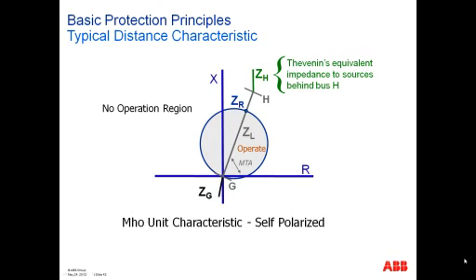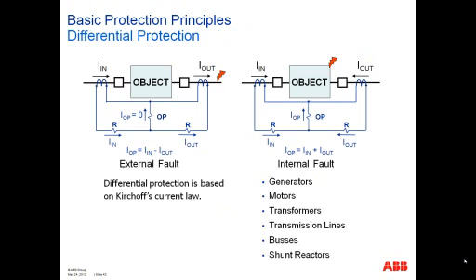Typical distance characteristics. For a mho unit characteristic, which is self-polarized, you have the circular characteristic that goes through the origin and the set reach. And the set reach is, of course, the diameter of the circle there that I show on the impedance plane. The impedance plane shows both the resistance and reactance direction.